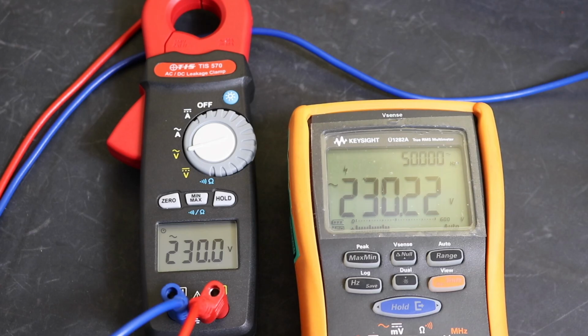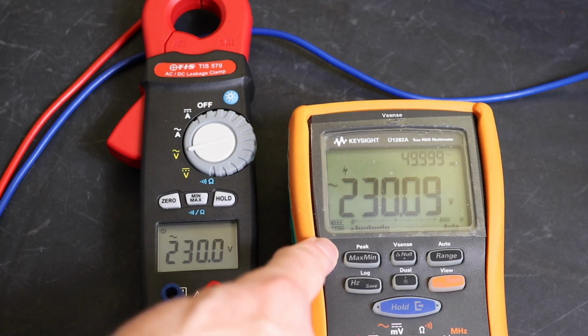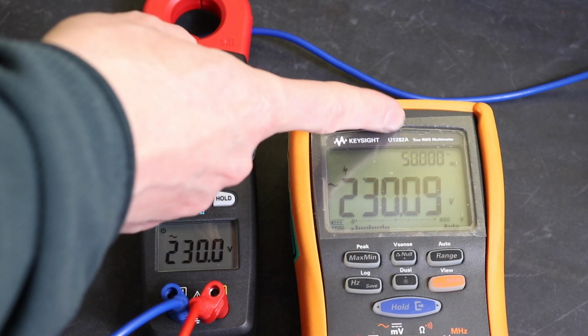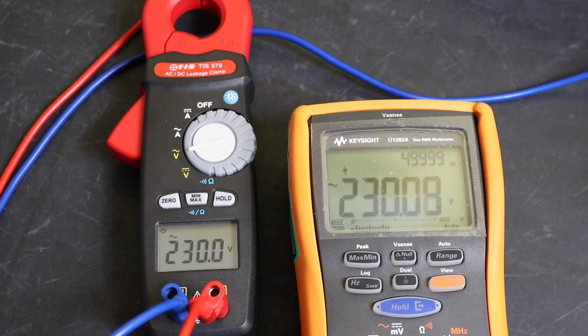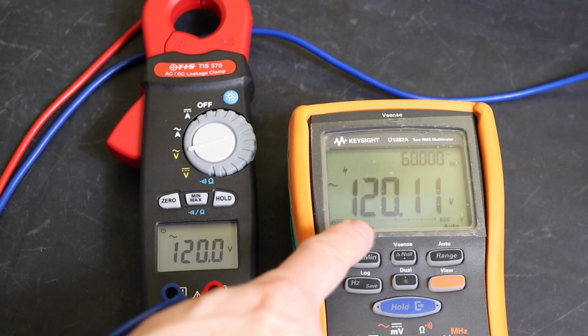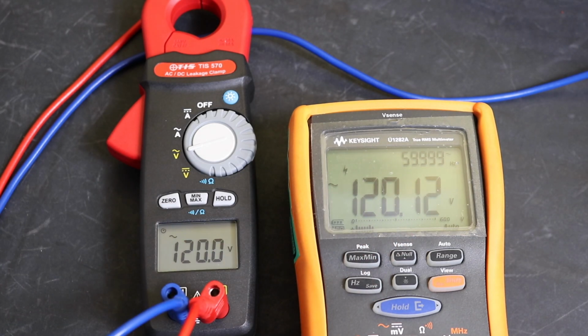So we are injecting some volts from our SMRT injection test sets. We are set up to read AC. You can see our Keysight here is displaying 230 and 50 Hertz there, and we've got 230.0 volts on our TIS570, which is all good. We'll just convert this to 120 volts for our American friends and 60 Hertz.